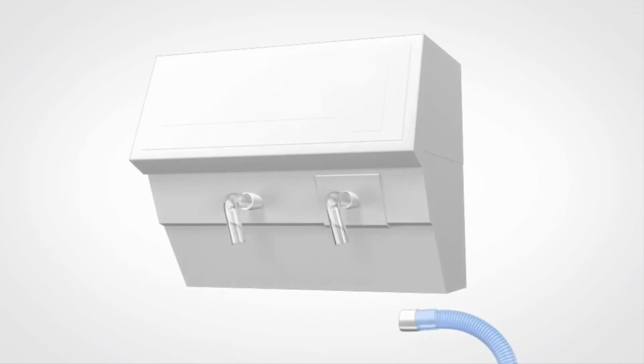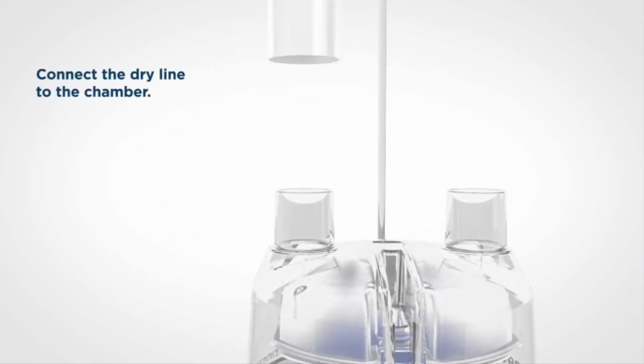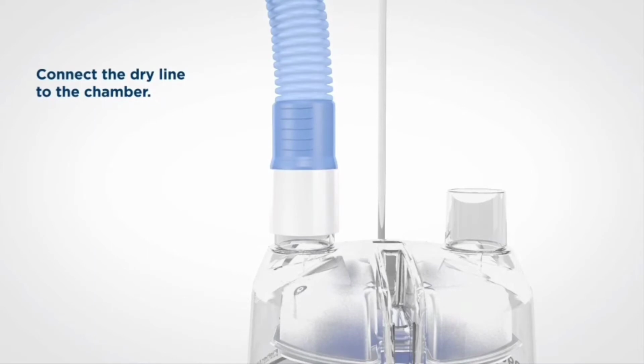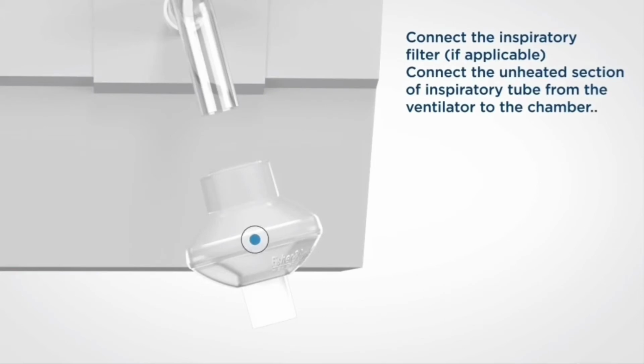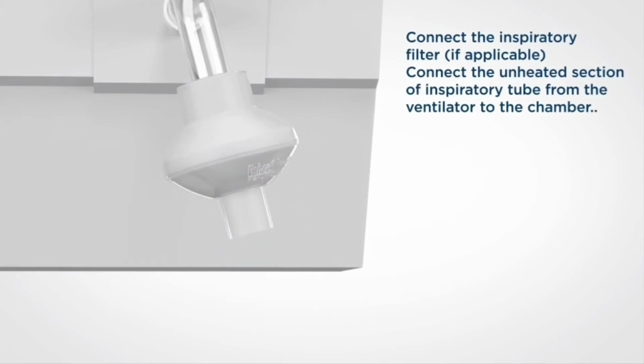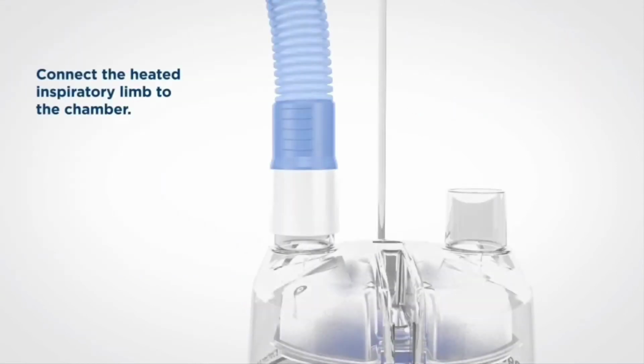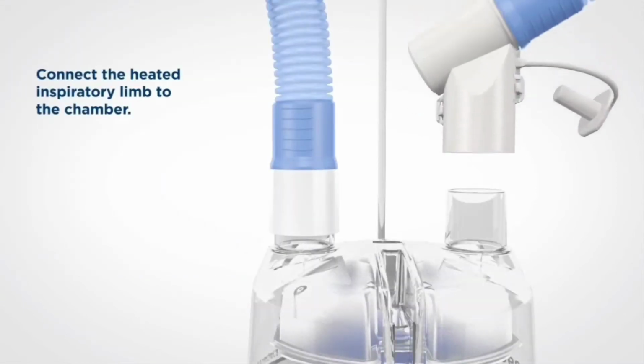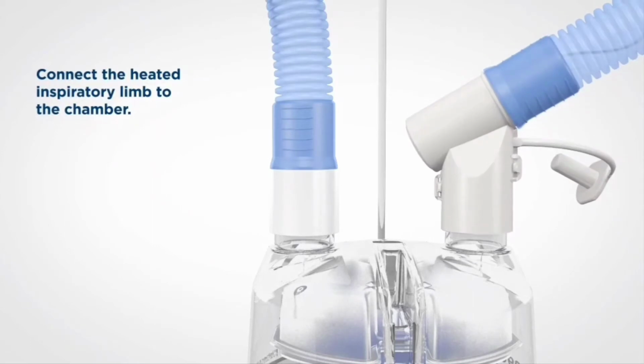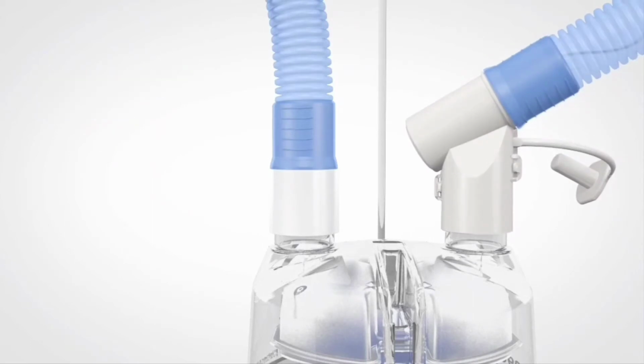Connect one end of the short piece of blue corrugated tube or dry line to the inspiratory port of the ventilator, and the other end to one of the ports on the humidification chamber. Either port may be used, but the left side, opposite the sockets on the humidifier, is preferable. If you're using an inspiratory filter, connect it between the inspiratory port of the ventilator and the dry line. Connect the white elbow-shaped connector of the blue corrugated inspiratory limb to the other port on the humidification chamber.